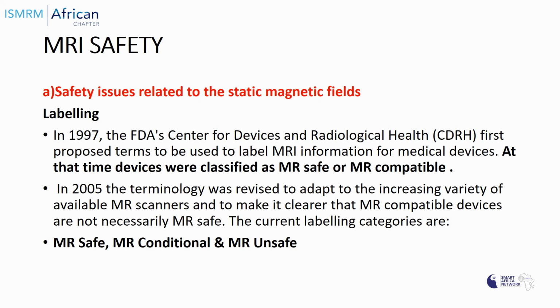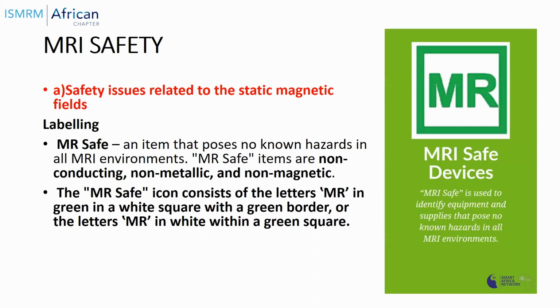The current labeling categories are therefore, we now have MR safe, MR conditional, or MR unsafe. These are the three types of labeling that we now have. MR safe items. They are an item that poses no known hazards in all MR environments. So MR safe items are non-conducting, non-metallic, and non-magnetic. What is the sign or the symbol? The MR safe consists of the letters MR in green in a white square with a green border, or the letters MR in white within green square. This is MR safe.